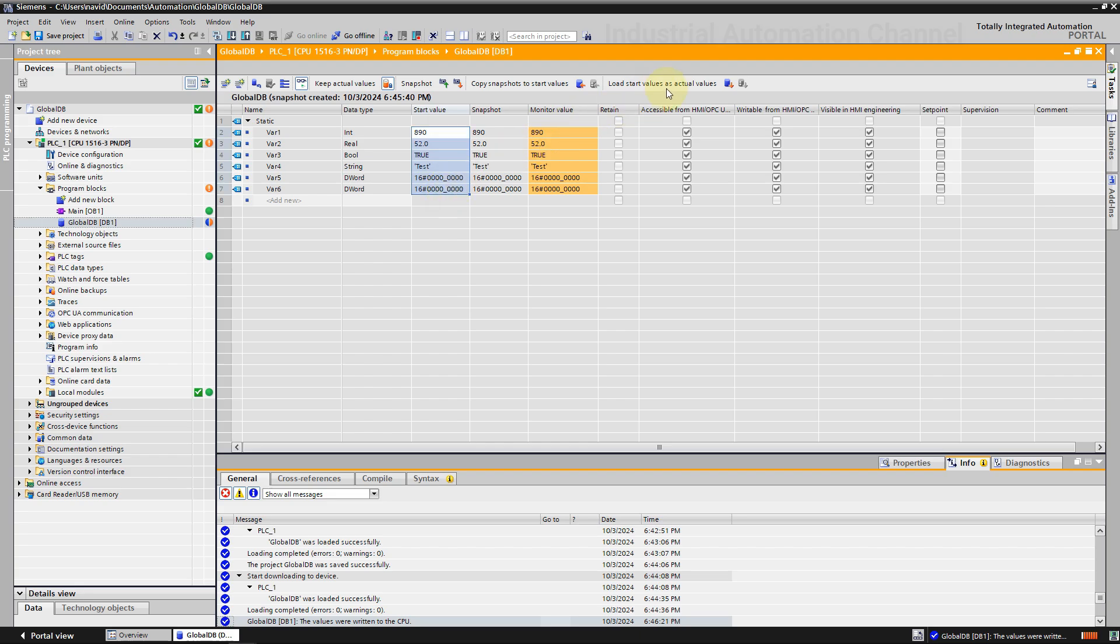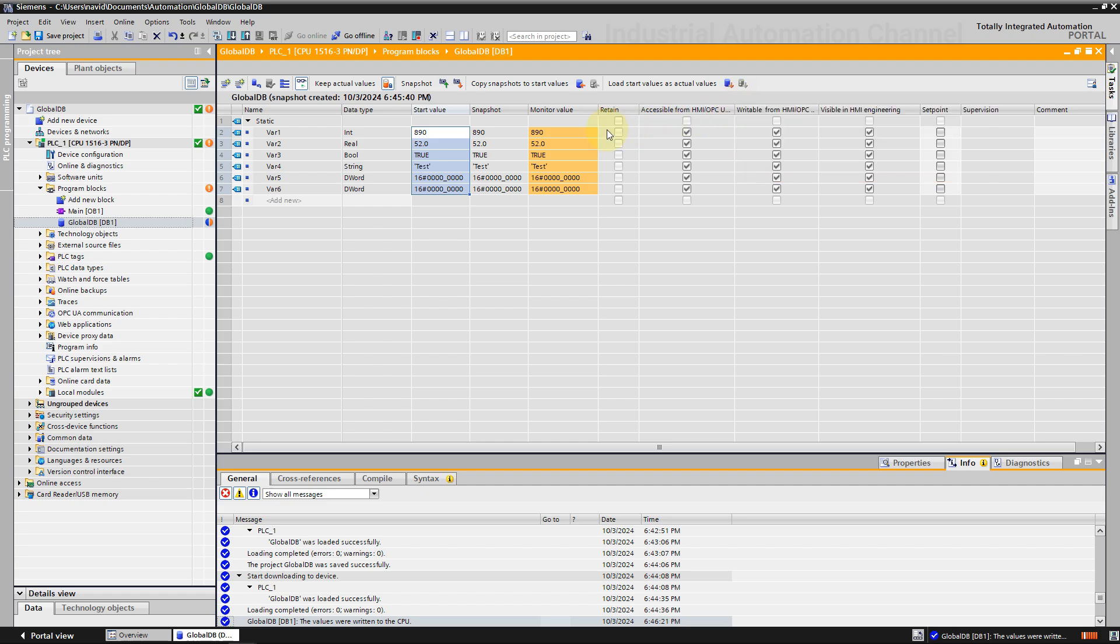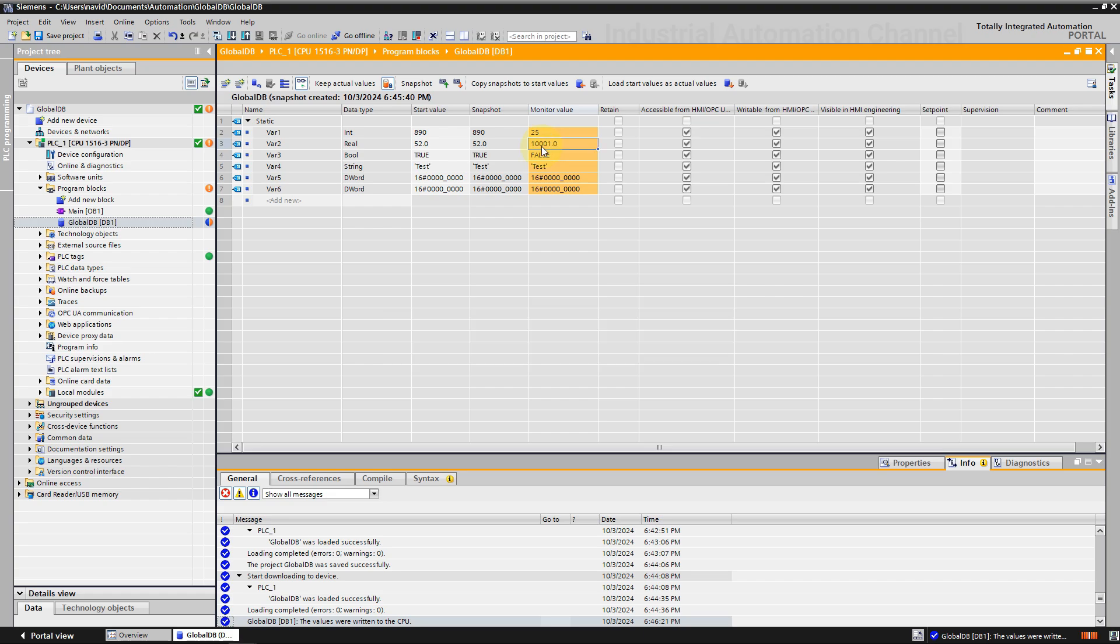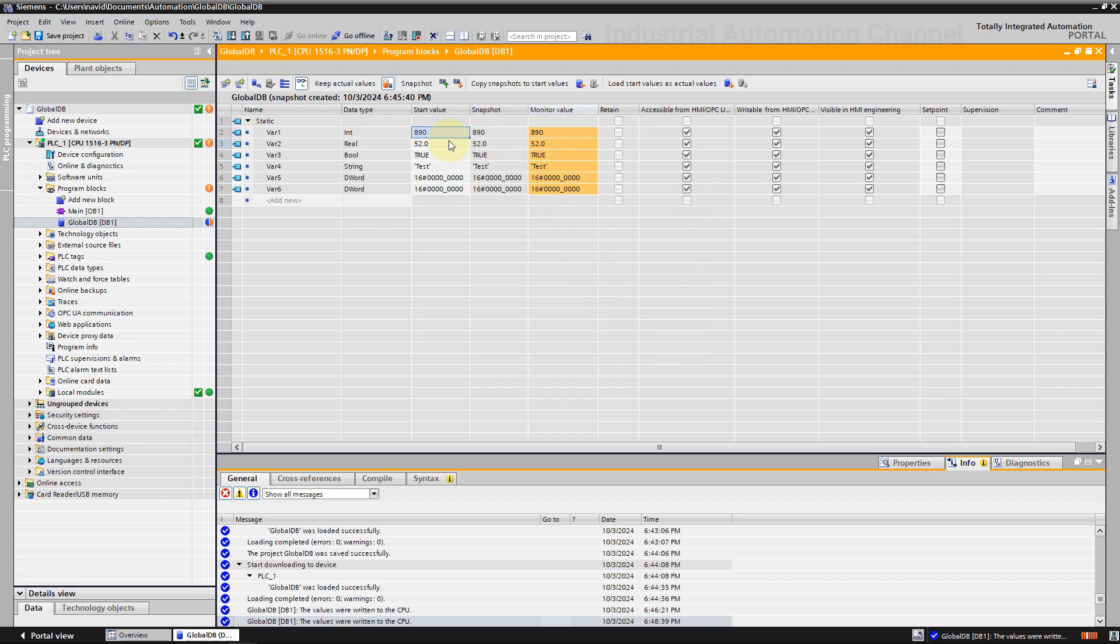Next option, you have changed the values and now you want to load the start values back into the actual values. It can copy all start values to the actual values by clicking this icon or only the set points for the tags whose set point checkbox is selected. Let me change some values. As you see, now all the start values are again the actual values. So with these options you can change the current value of the variables or make the change back. All right, we learned how to create a global DB in TIA Portal and now we need to have access to the variables that we have created in this DB to use them in our code.